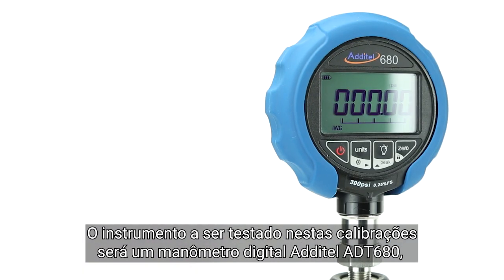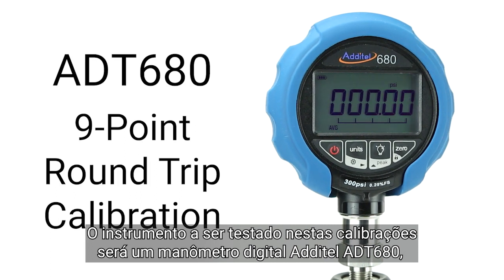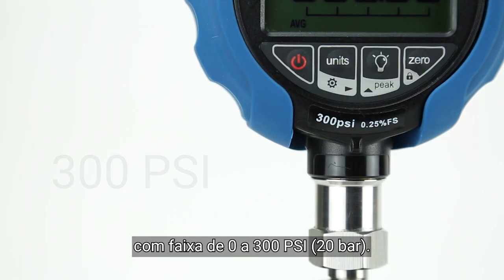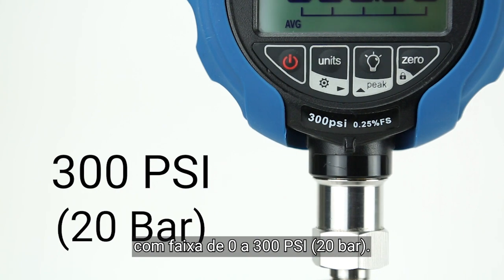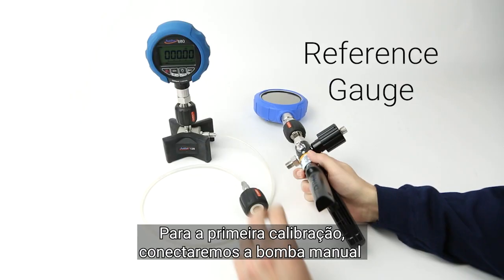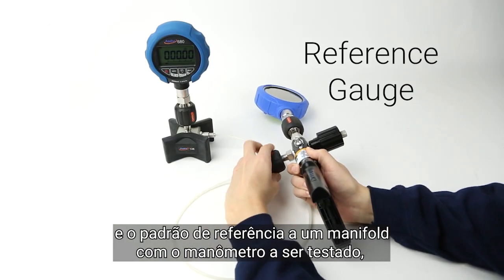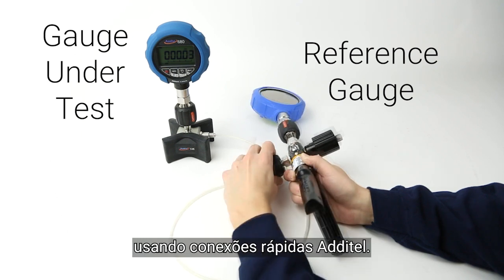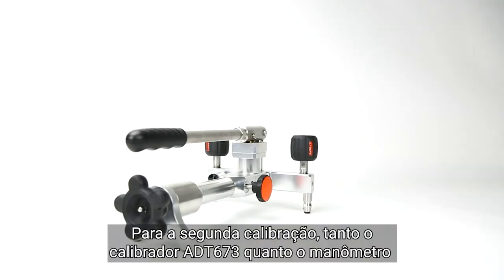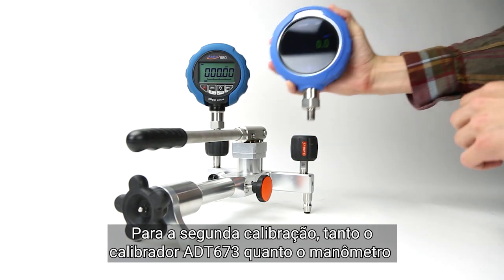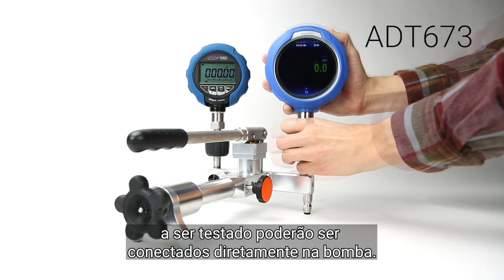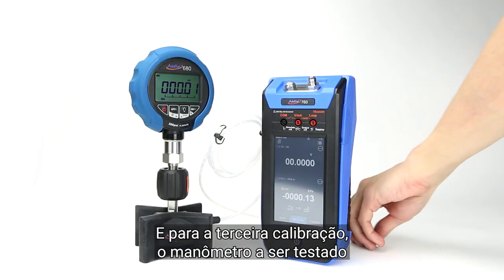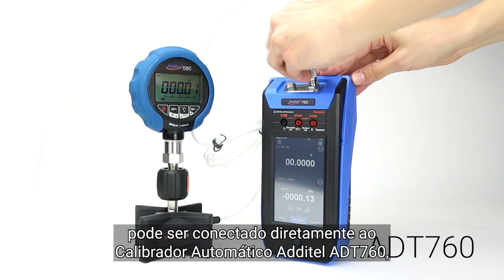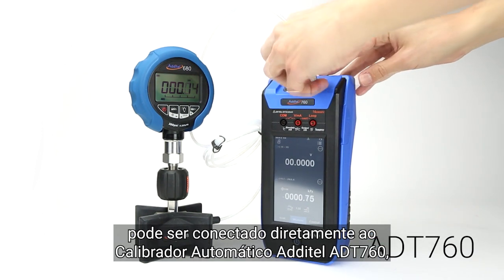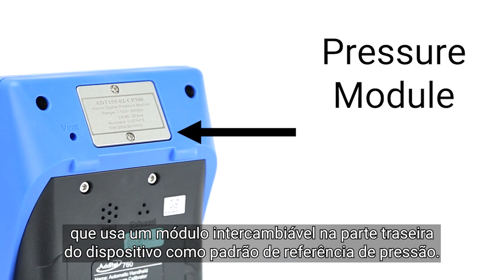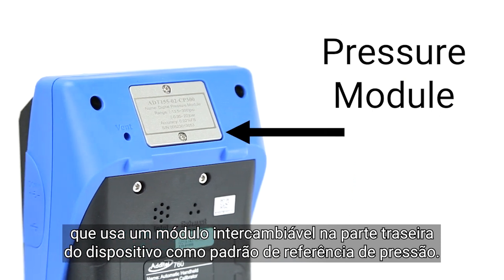The device under test for the calibrations will be an Additel 680 digital pressure gauge, with a range from 0 to 300 psi, or 20 bar. For the first calibration, we'll connect the hand pump and reference gauge to a manifold with the gauge under test, using Additel quick connectors. For the second calibration, both the 673 calibrator and gauge under test can be connected directly to the pump. And for the third calibration, the gauge under test can be directly connected to the Additel 760 automatic calibrator, which uses a swappable pressure module on the back of the device as the pressure reference.